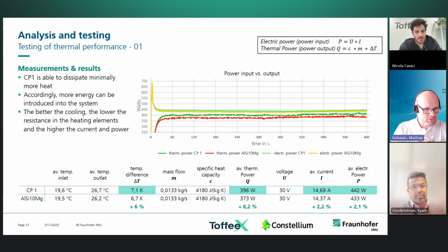Still, we see a bit of difference in temperature between inlet and outlet, specifically for the CP1 and the silicon 10, using the exact same settings. You can see the CP1 performs a bit better: only a temperature difference between inlet and outlet of 6%, but it allows a bigger power draw. So if this were a computing unit, you could basically have more computing operations, or run your CPU faster by 6%, and that can add up to quite a lot.